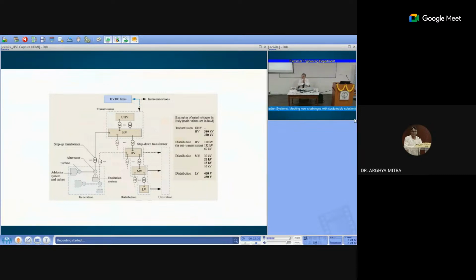Perfect. So we need to say that the losses do not depend on the voltage. If you have a resistance at a level of 1 volt or 100 kilovolt, the losses inside the resistance depend on the current going through, not on the level of the voltage. So since the losses depend on the square of the current, we want to transmit the power at the lowest level of current. So we increase the voltage when the distance is important, otherwise most of the power is lost in the line.